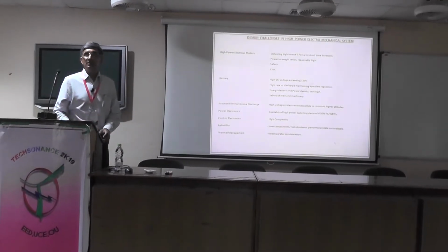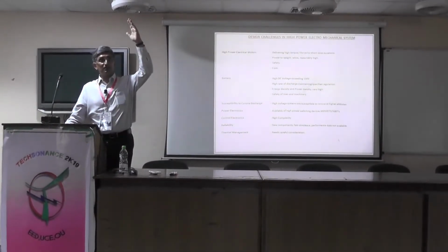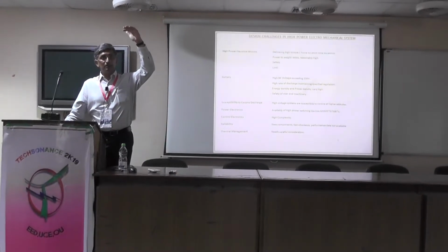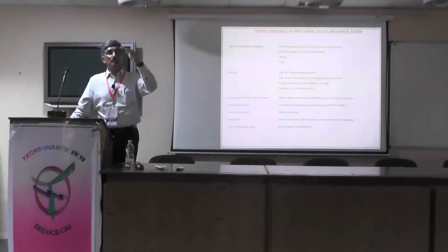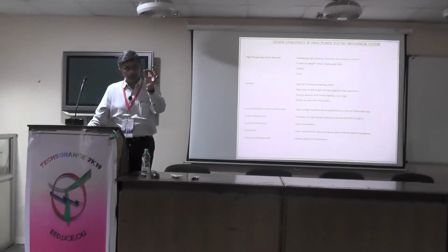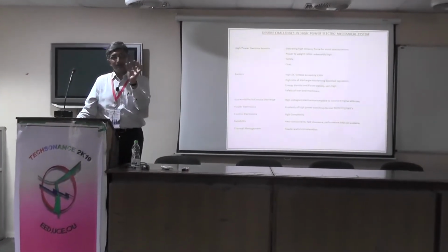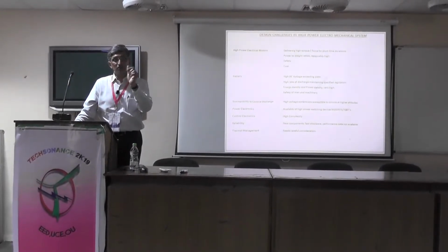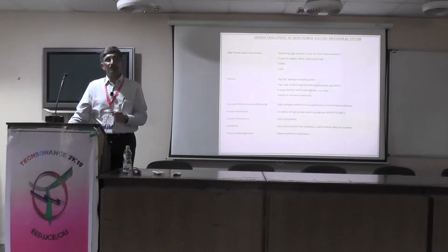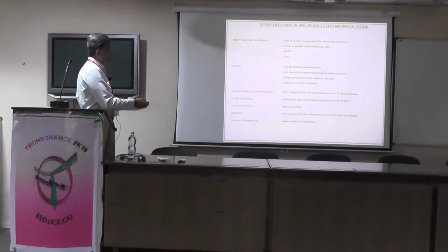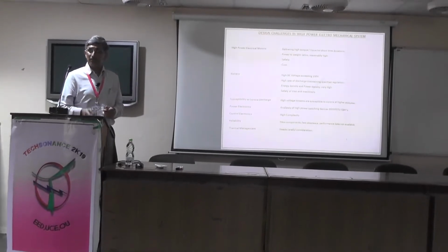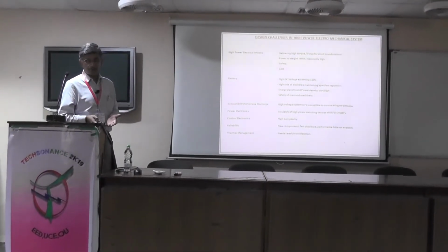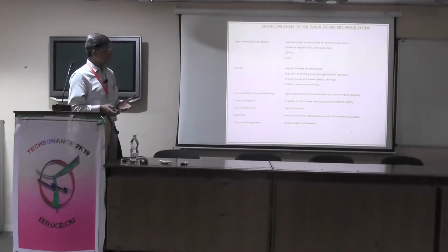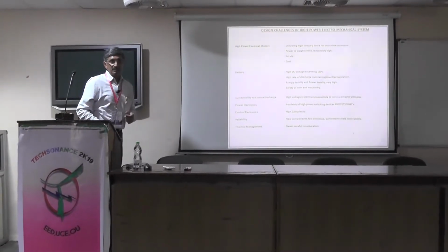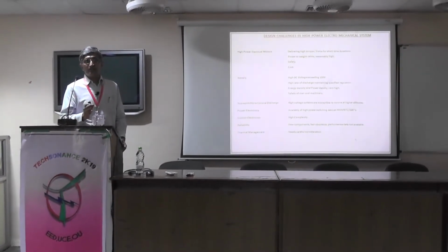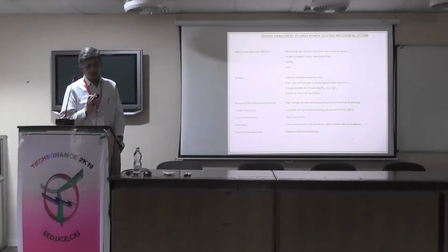Corona is a challenge, because the higher the reaches of the atmosphere you go, the dielectric strength of air goes down. Once that happens, the same voltage with the same gap starts discharging, causing a short circuit. So you have to take adequate care in your design. If it exceeds 150 volts, that's what literature tells us - below 150 volts nothing happens. Anything exceeding 150 volts DC, you need to have enough care in your design to take care of current discharge at higher altitudes.